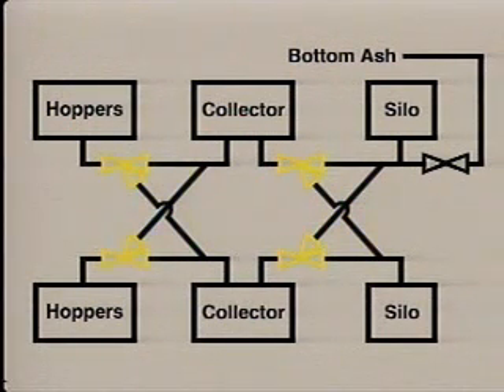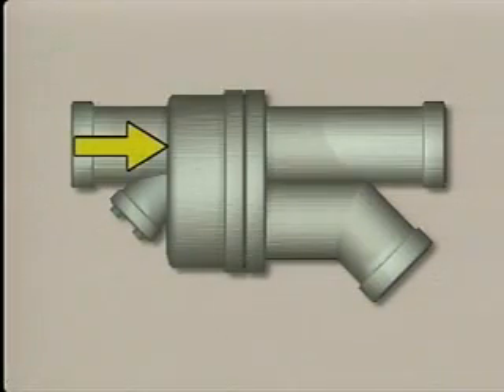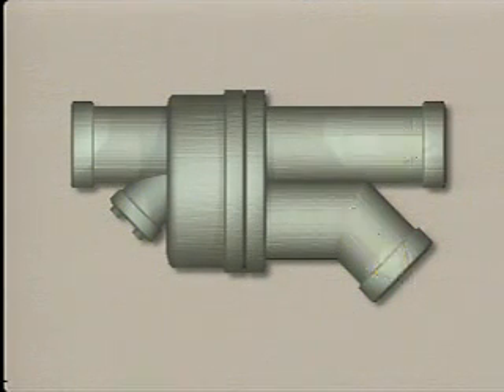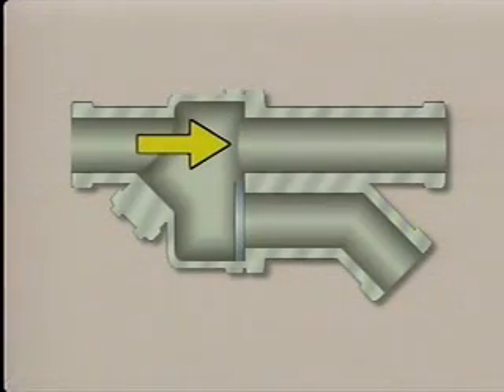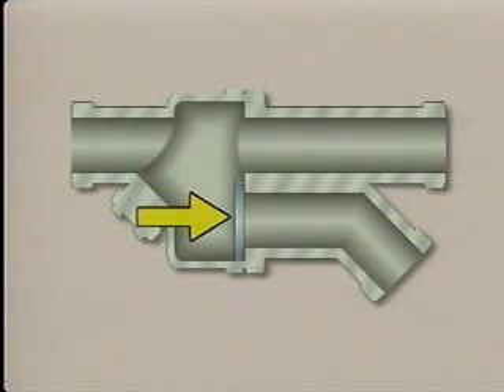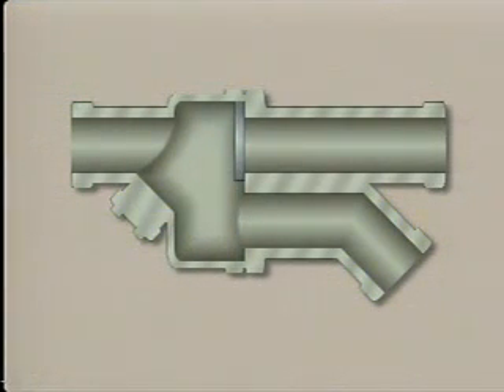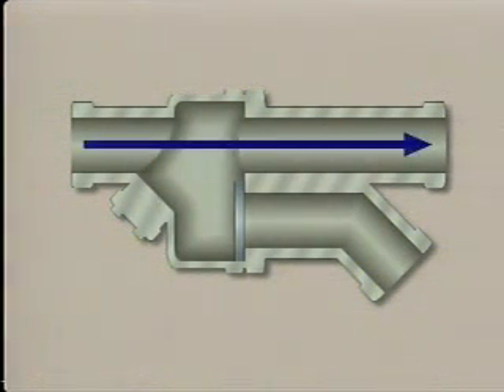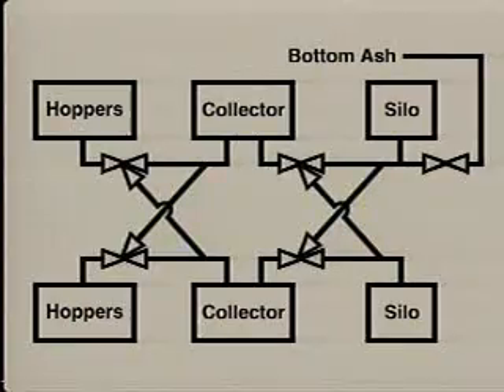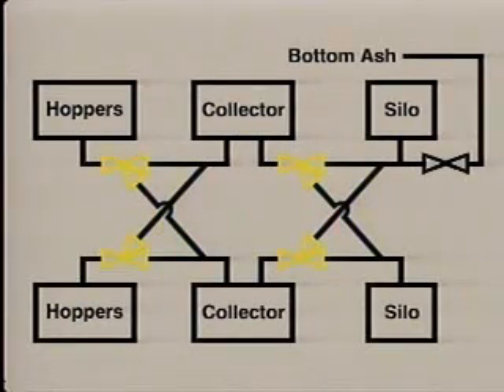These crossover valves, which are sometimes called diverter valves, allow the fly ash to cross over from one system to the other. A crossover valve has one inlet port and two outlet ports. Only one of the valve's outlet ports is open at a time. The other outlet is closed. Changing the position of a disc inside the valve changes which outlet is open and which outlet is closed. Therefore, there are two possible paths for the fly ash through a crossover valve: the normal straight-through path or the crossover path. These crossover valves can change the flow path of the fly ash as it moves through the process.